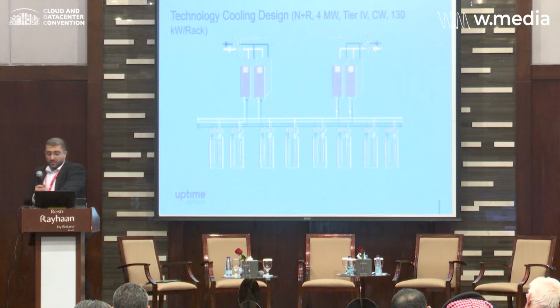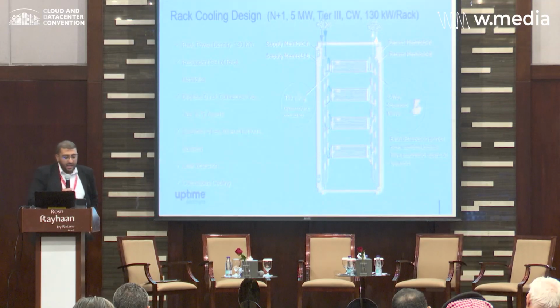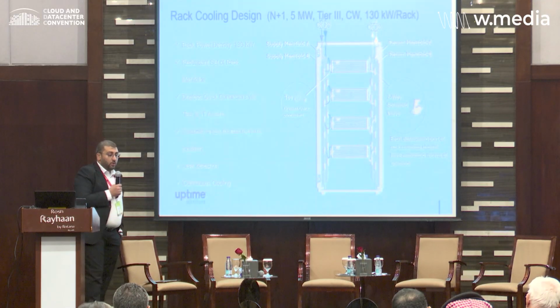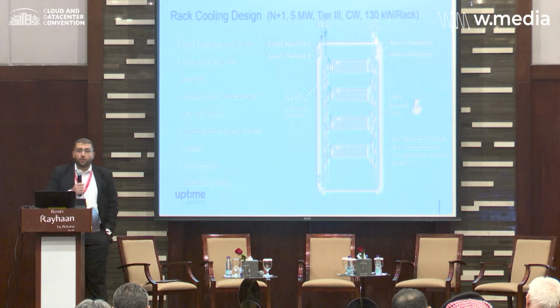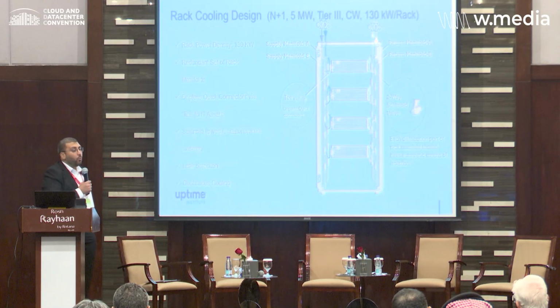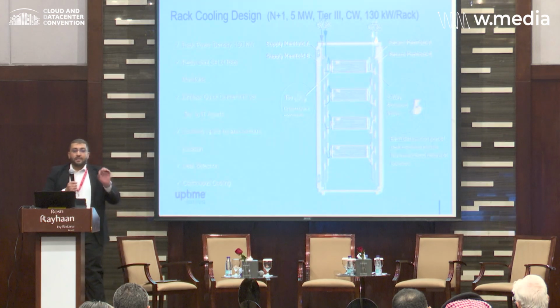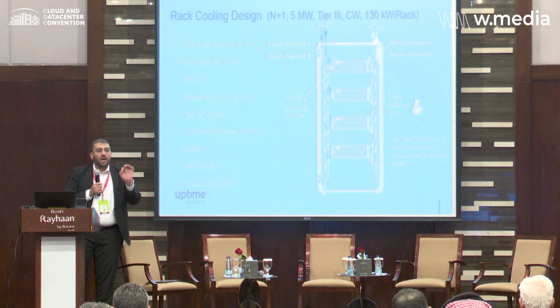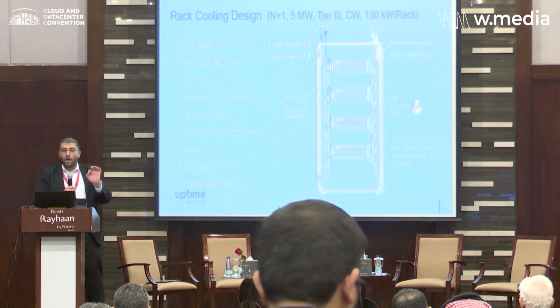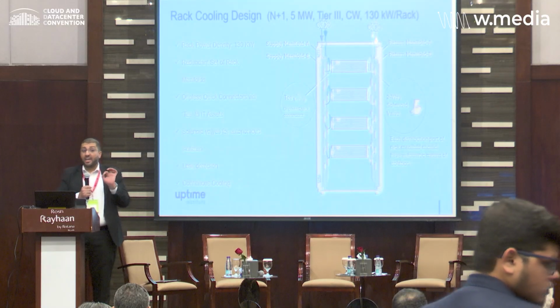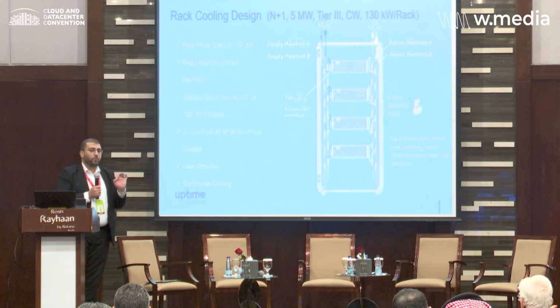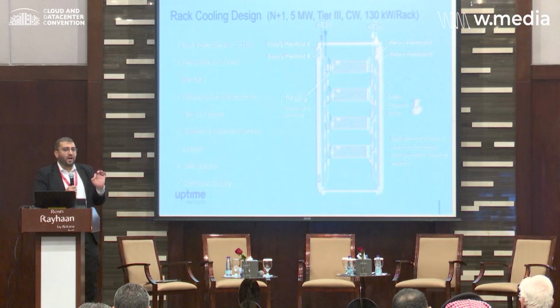Now, let's have a look inside the racks. In Tier 3, we have a dual manifold where the dripless connector connects to the IT assets. What we have in addition to that to achieve Tier 4 is a solenoid valve. The purpose of the solenoid valve is to detect the leak, isolate the leak, and sustain the operation of the AI workload, and most importantly, to protect the IT asset.